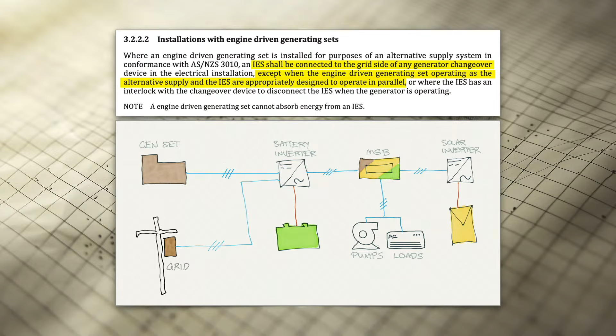Now, you might go, oh, hang on, there's plenty of systems that can actually parallel with another source even when the grid's not available. And what does that mean? Well, there's an exception. It says, except when the engine-driven generating set as the alternative supply, and the IES are appropriately designed to operate in parallel.